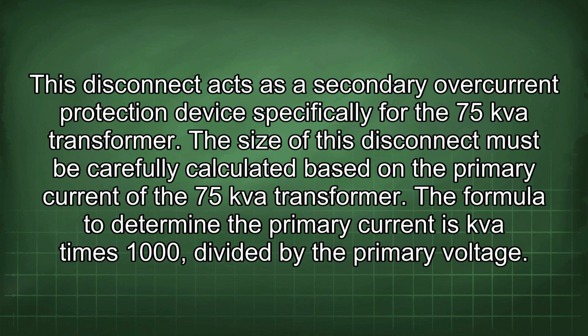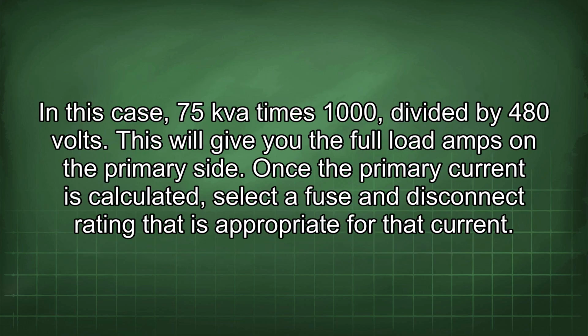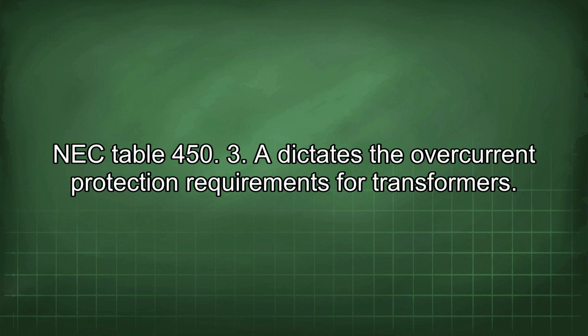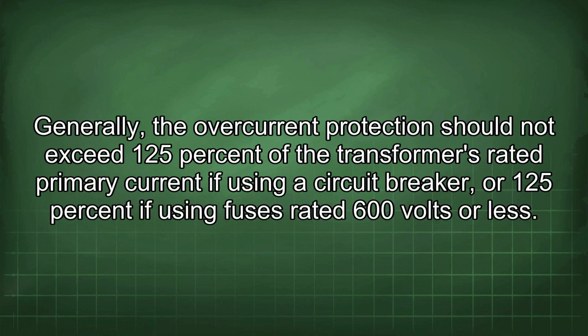The formula to determine the primary current is kVA times 1000 divided by the primary voltage. In this case, 75 kVA times 1000 divided by 480 volts. This will give you the full load amps on the primary side. Once the primary current is calculated, select a fuse and disconnect rating that is appropriate for that current. NEC Table 450.3 dictates the overcurrent protection requirements for transformers. Generally, the overcurrent protection should not exceed 125% of the transformer's rated primary current if using a circuit breaker, or 125% if using fuses rated 600 volts or less.